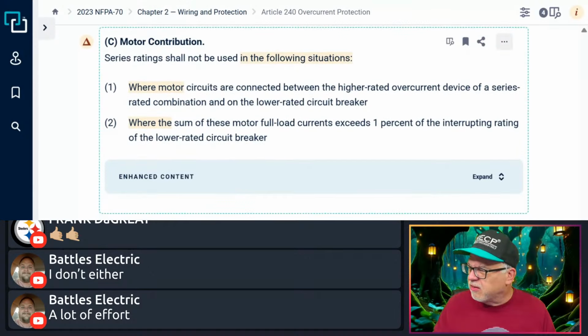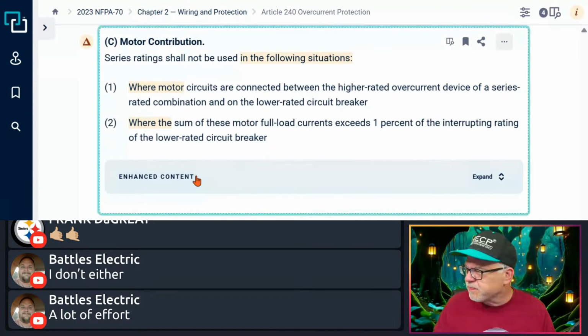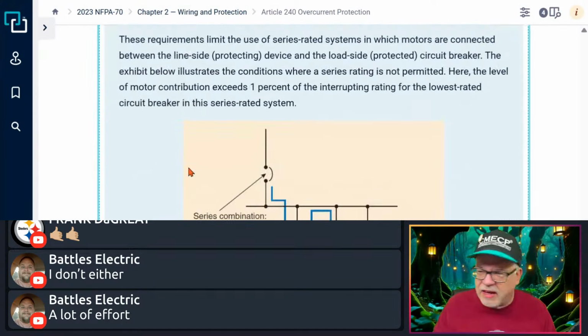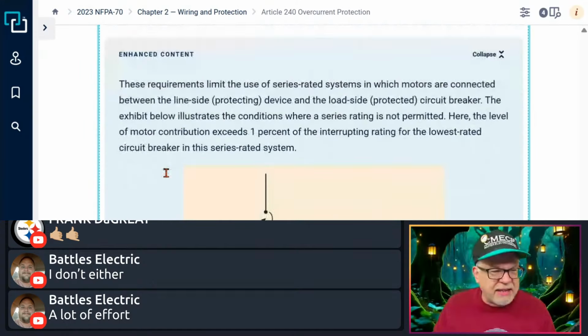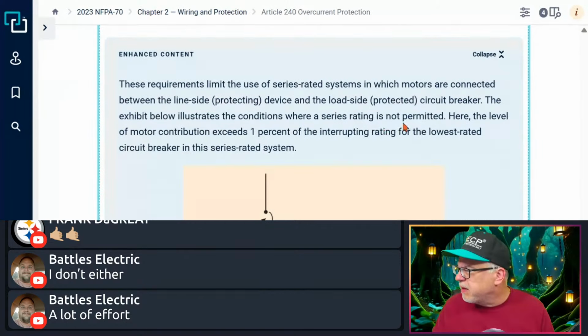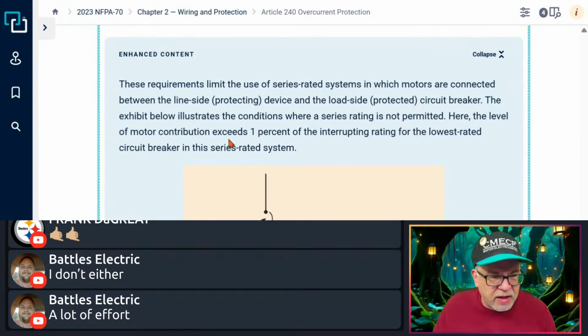It says, again, this is verbatim of what we just read. And this is kind of an example here. Because I like to look at these enhanced, it says the requirements limit the use of a series rated system in which the motor is connected between the line side protecting device and the load side protected device. It says the exhibit shown illustrates the conditions where the series rating is not permitted. Here, the level of motor contribution exceeds 1% of the interrupting rating of the lower rated circuit breaker.